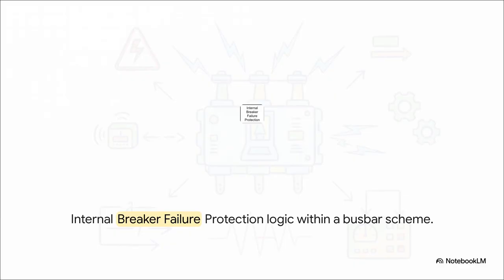Looking at the logic block here, you can see it doesn't just sit off in its own little world. The internal breaker failure protection block is deeply baked right into the broader busbar protection scheme. It constantly communicates with the trip logic and zone selection arrays to seamlessly route those emergency trip commands exactly where they need to go if that primary breaker fails.